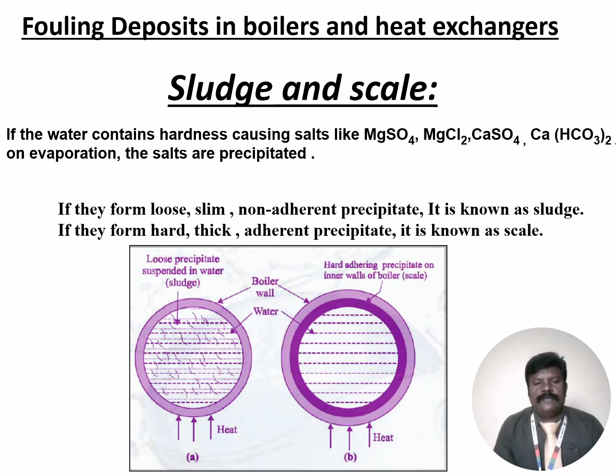Here the suspended impurities may be sludges, and the thin, slimy deposition we may call sludges. Here, the thick material we may call scale. And all molecules are strongly attached on the boiler wall, which cannot be easily removed from the boiler. But the sludge material can be easily removed from the boiler by blow down operation or some other technique. Here, the scale cannot be removed by blow down operation, but it can be removed by hammering method, wire brush operation method, by treating with EDTA solution, or by using dilute sulfuric acid and other methods.